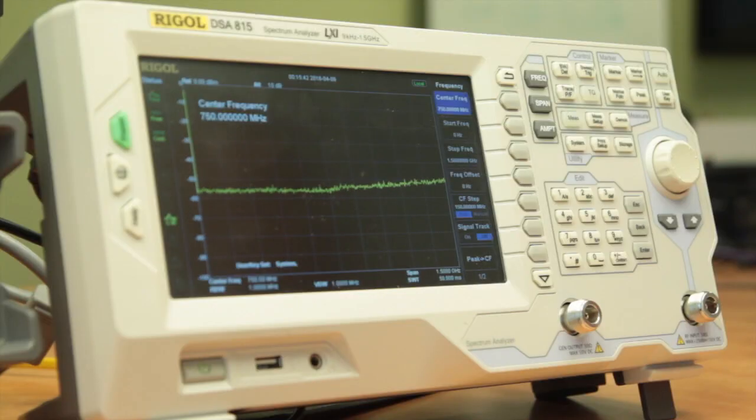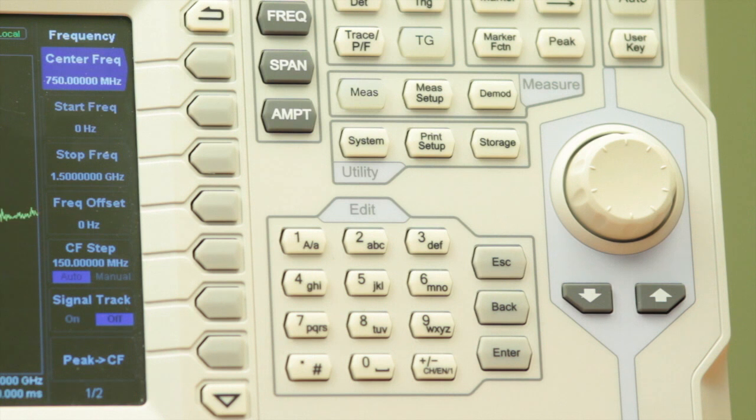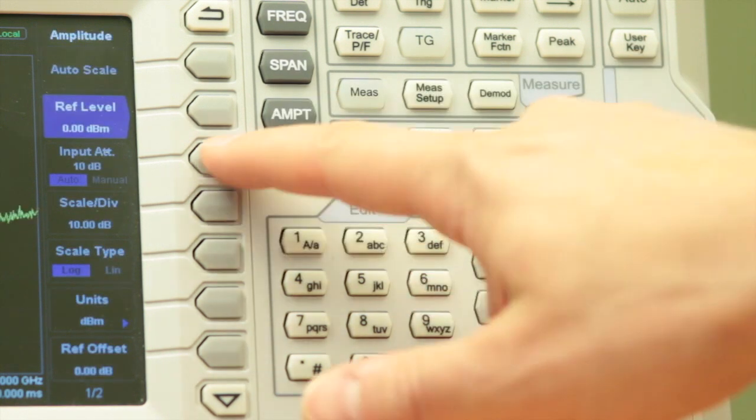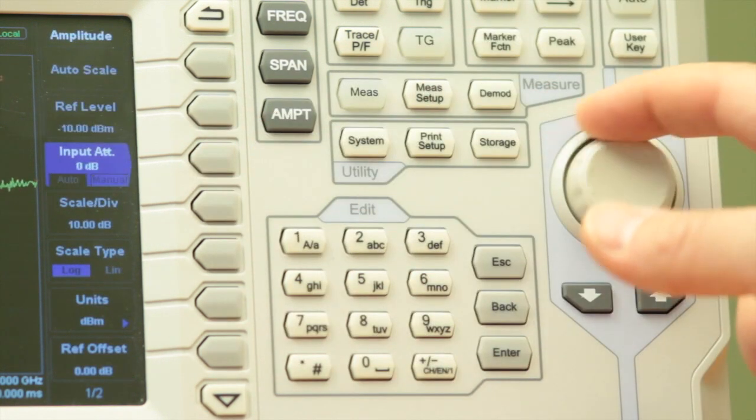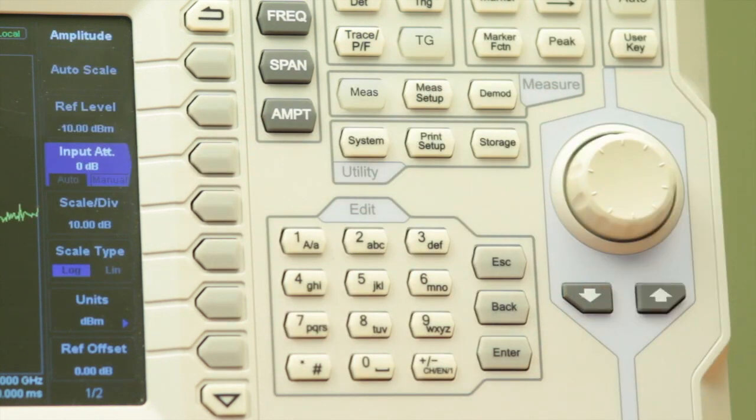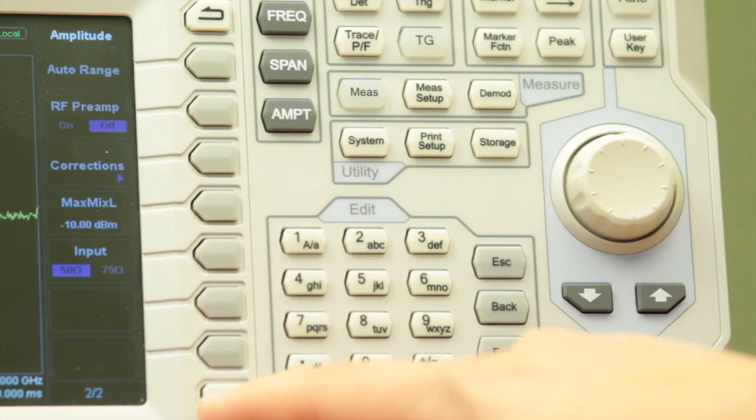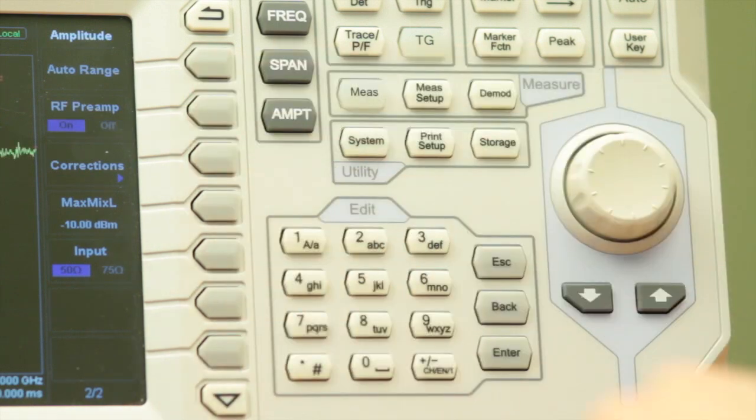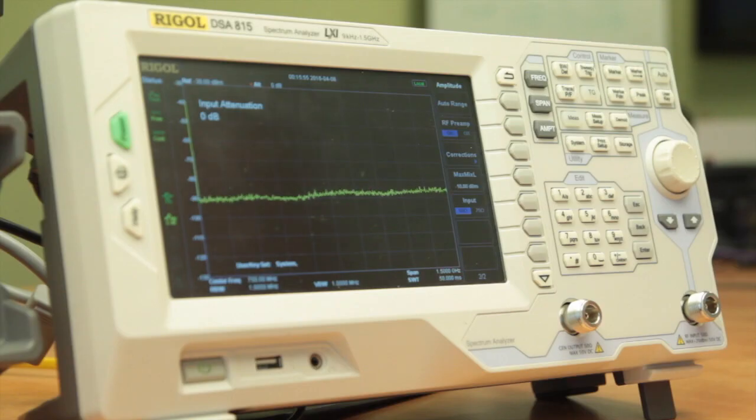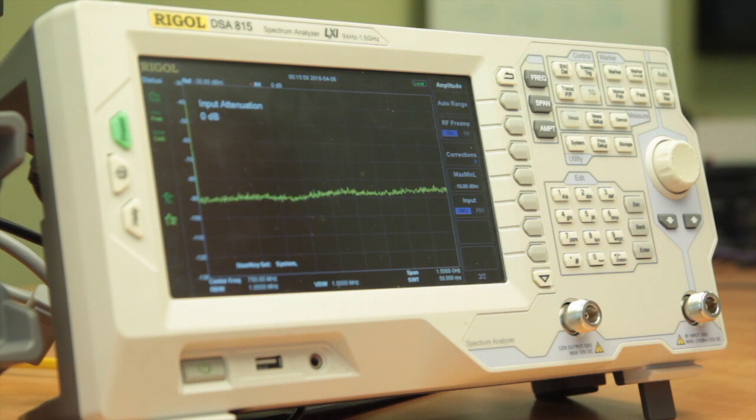The first thing we're going to do is go into our amplitude menu. Turn the internal attenuator down and turn the RF preamp on. This is the best setup for these kind of measurements because we have a fairly low signal level and it gives us the best way to measure this.